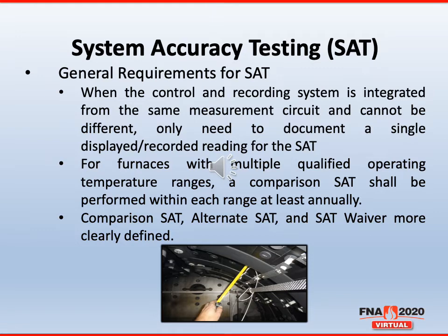A comparison SAT, if that's the method being chosen, shall be performed within each range at least annually. For example, if you have a class 2 plus or minus 10 range from 800 to 1500, class 3 from 1500 to 1800, and class 5 from 1800 to 2200, an SAT at least once a year will need to be conducted in each of those ranges. So the plus or minus 10, the plus or minus 15, and the plus or minus 25. It doesn't necessarily have to be conducted all at the same time, but at least on an annual basis, all three of those ranges are covered.